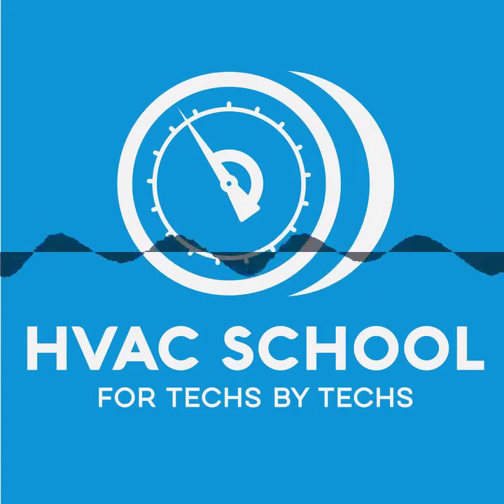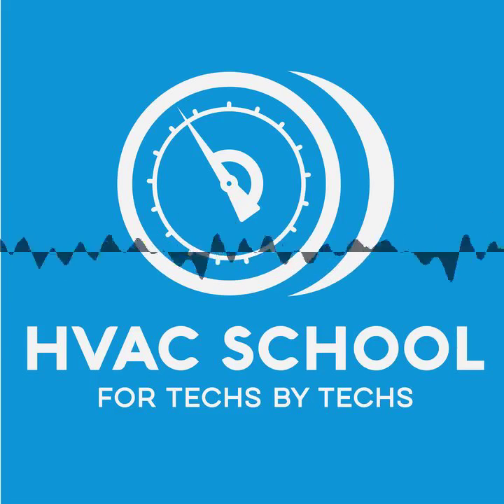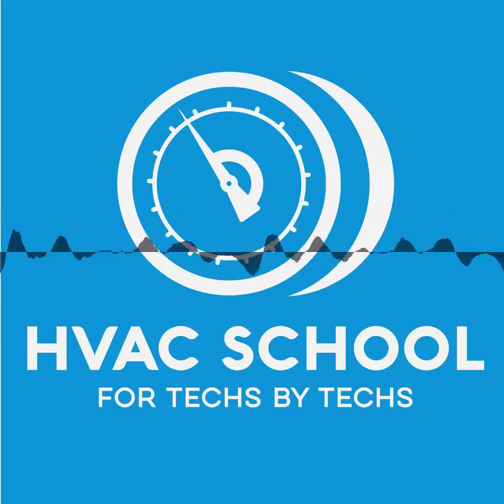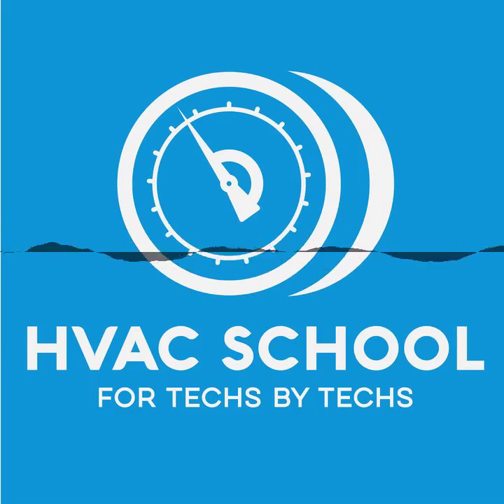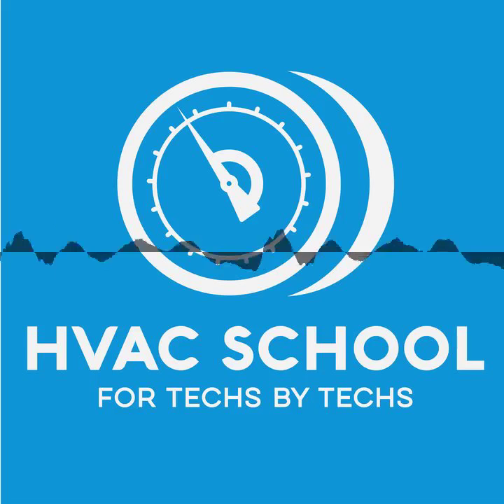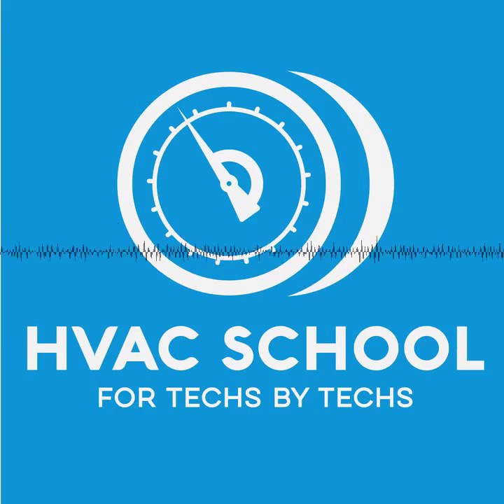So this is why you need to insulate the condensate lines. And there have been times where I get a phone call and there's puffs of smoke coming out of it. They're complaining, they don't know what's going on, and it's actually just fog. That's how cold it's going. Right. It's actually hitting the air in the space. The air in the space is actually condensing onto the cold air that's exiting the unit. Yeah, where the relative humidity isn't high enough to cause dew, but it's high enough to cause fog.